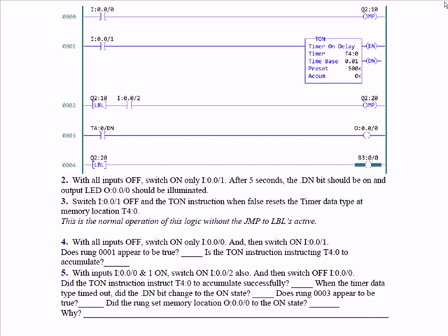If you scan down through the program, you can see in rung 2 there's a label 10. Which means if rung 0 is true, you're going to skip rung 1. It will be literally as if the rung was not even in the program. And then in rung 2, if that rung is true, if input 2 is on, the output instruction is a jump to label 20. If you scan down, you'll see label 20 is the last rung, rung 4, and rung 4 is an unconditional rung, meaning it has no permissives.